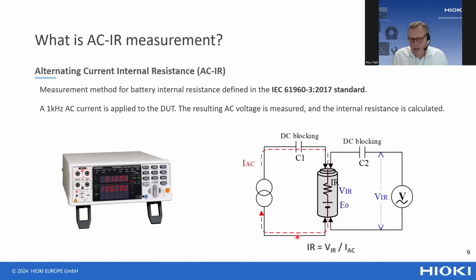The measurement is done in accordance with the IEC 61960-3 standard, which describes how to do the measurement. The standard specifies that the frequency of the AC current signal must be 1 kilohertz. This is important because the internal resistance is frequency dependent. When you want to compare tests performed, for instance, in China with a test performed in Europe, you need to make sure you do the test at the same frequency.